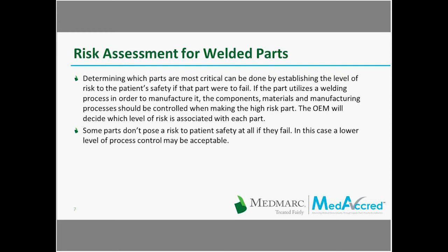Risk assessments are really critical. As parts become more risky, you usually need a higher level of understanding of how that part functions — looking at the metallurgy and the mechanical properties of that weld. You want to do more testing as the risk increases. Some considerations when designing a weld: What's the function of the device? What kind of stress is it going to see — is it something that's beaten on repeatedly? Does it share the load, maybe threaded or pressed in before welding? That's not going to be as risky as if the weld bears all the load. You also want to look at where the instrument or device will be used — within the wound site or outside? If it fails, could there be fragmentation that could affect the patient? Could the nurse or surgeon be harmed? And even surgical delay matters — if the device comes in a kit with a duplicate, it may not be as risky as if the instrument fails with no replacement available.